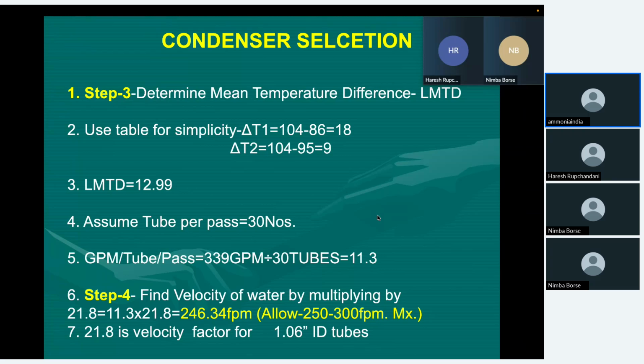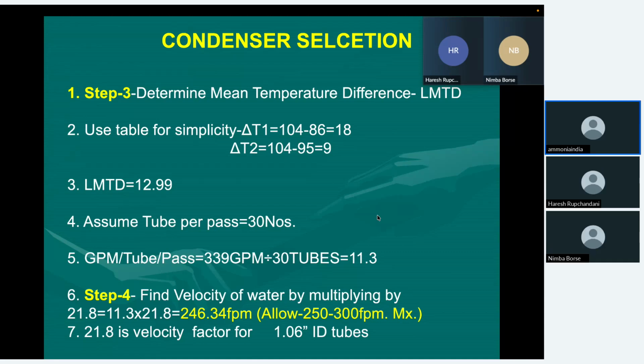The next step is to find the velocity of water by multiplying by 21.8. Now this 21.8 is a ratio for tubes which are 1.25 diameter or 1.06 internal diameter. This ratio will vary as the diameter of the tube changes. For 1.06 ID, it's 21.8. How this has been calculated is a detailed calculation. We are not going into detail of that, but if required, you can send me a mail and I will provide these calculations. Normally, we select a velocity of around 250 to 300 FPM so that the pressure drop and the pumping power come down.